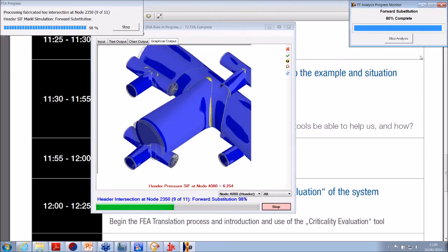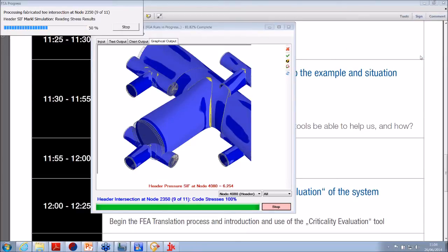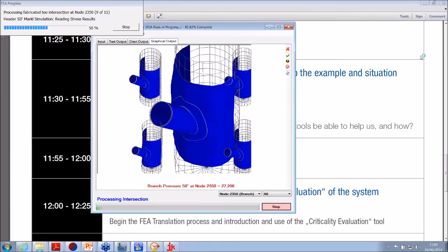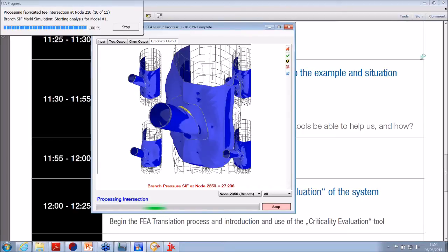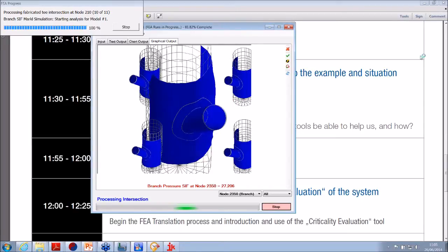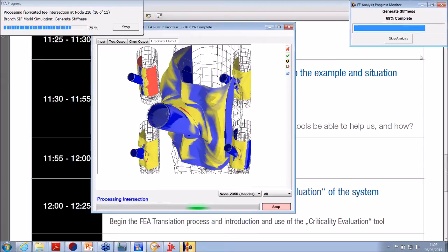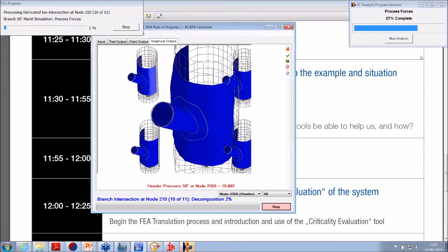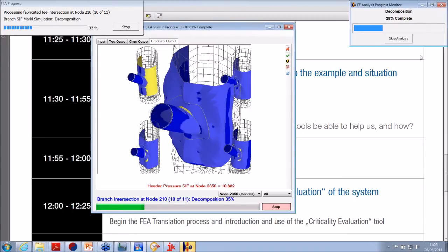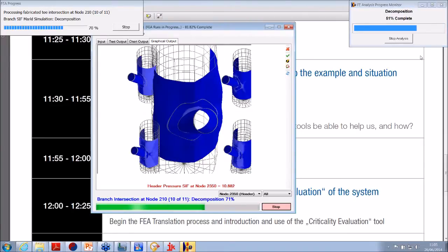There was another question, Janine? Yes. Is it possible in special cases to get a higher code stress pipe using FEATools against the B31 procedure, or is that out of the question? If I understand the question correctly, then yes, the possibility of the stress increasing using the FEA data compared to the B31 data is certainly possible. Yeah, I would say absolutely.